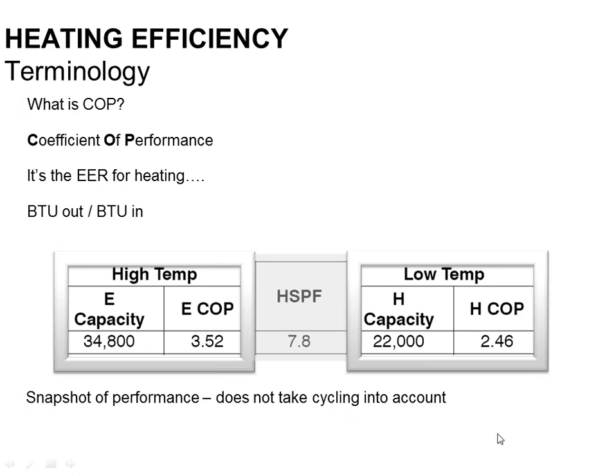So here's an example of a heat pump. This is not even the heat pump we're talking about today with variable speed. This is just a regular heat pump, a regular 7.8 HSPF legal minimum heat pump. Now remember, the heat pump we're talking about today is 12 to 13 HSPF. But even this regular one has a COP on a 47-degree day of 3.52, and on a 17-degree day 2.46. So what's a COP, right? COP is coefficient of performance. We're comparing one heat pump to the other. We don't really look at this.